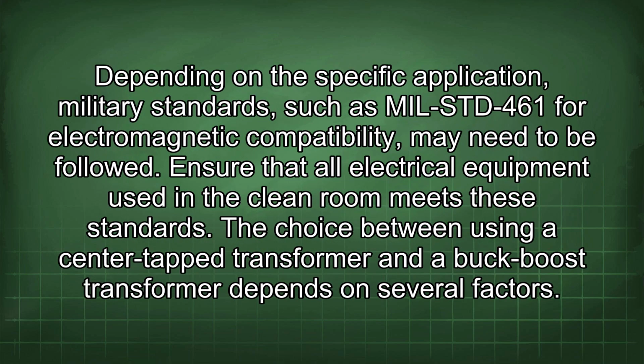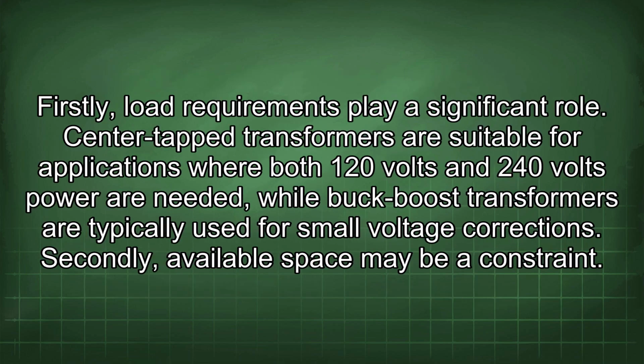Depending on the specific application, military standards such as MIL-STD-461 for electromagnetic compatibility may need to be followed. Ensure that all electrical equipment used in the clean room meets these standards. The choice between using a center tap transformer and a buck-boost transformer depends on several factors. Firstly, load requirements play a significant role.